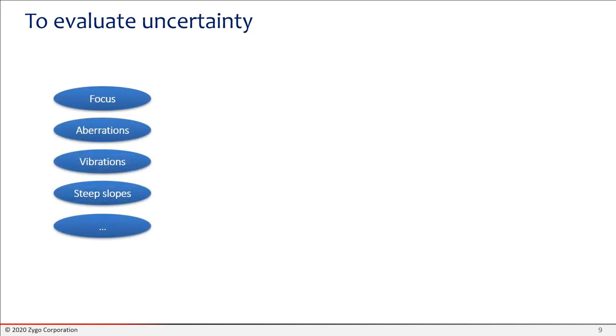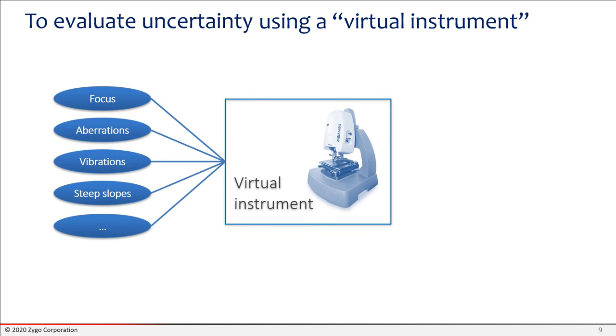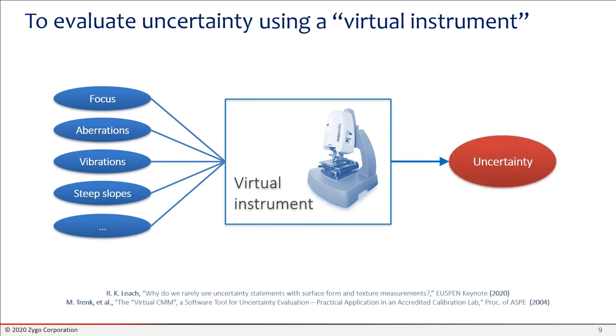Another thing you could do with a good interferometer model is to evaluate uncertainty. Suppose you've identified a series of sources of error, focus aberrations, vibrations, steep slopes, and so forth. You could certainly do some experiments to find out how those things are influencing the uncertainty of your final result. But it would sure be nice if you could just do that numerically in a computer, what's called a virtual instrument, and then you get an uncertainty at the other side. And there are a variety of different approaches that you could apply to this, including machine learning.